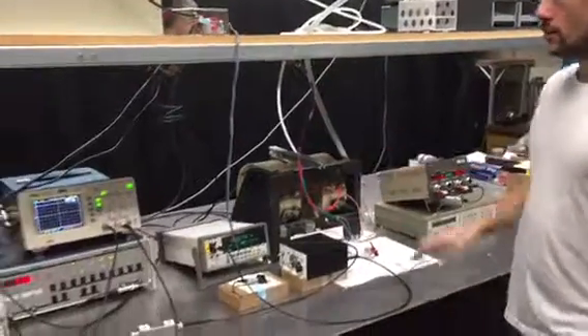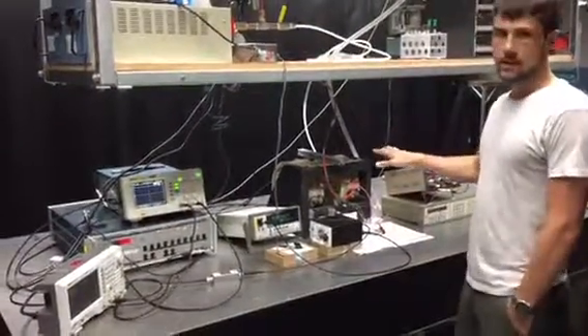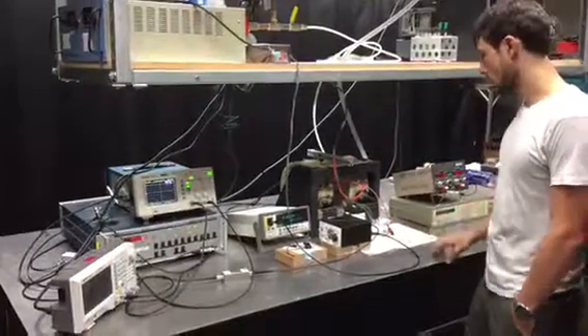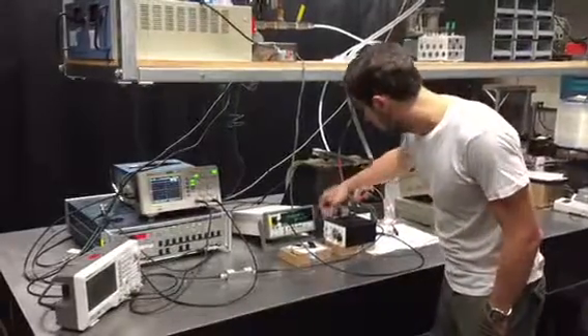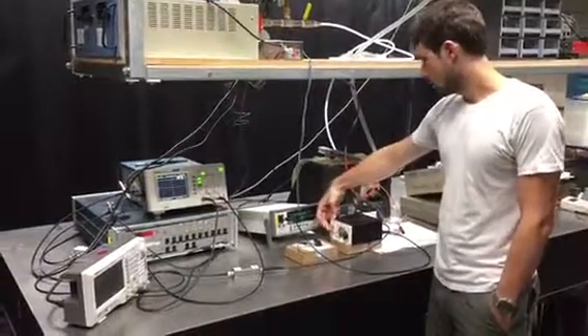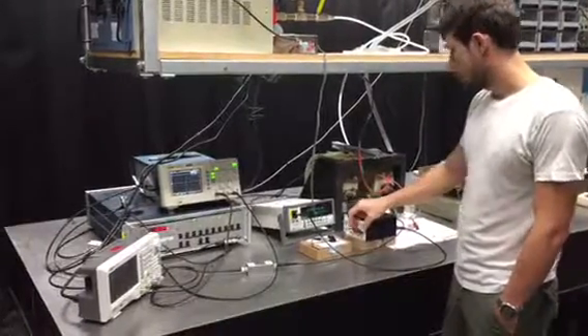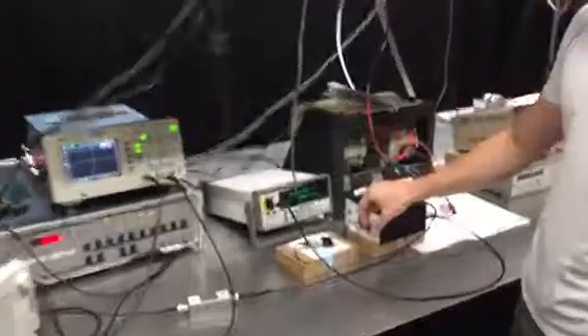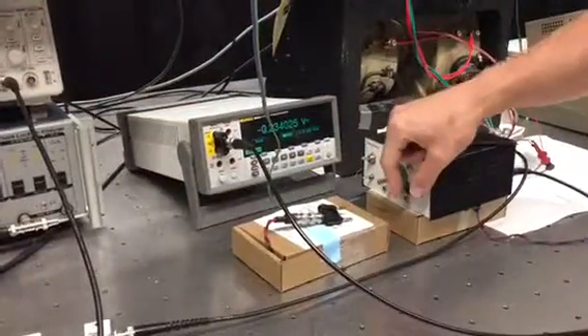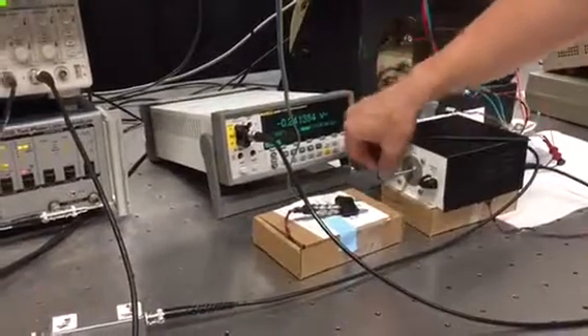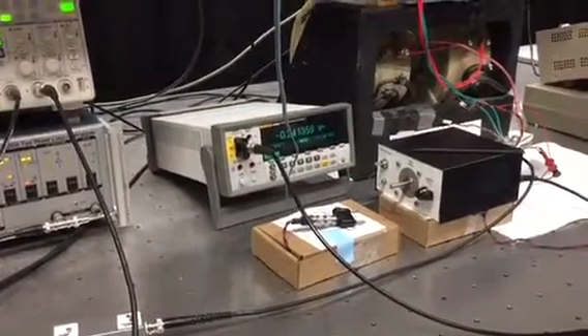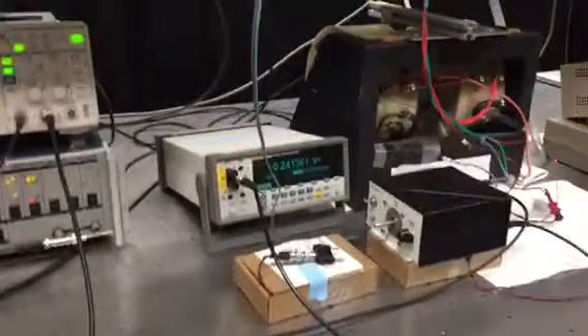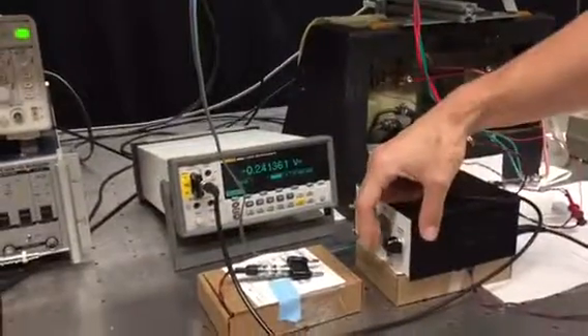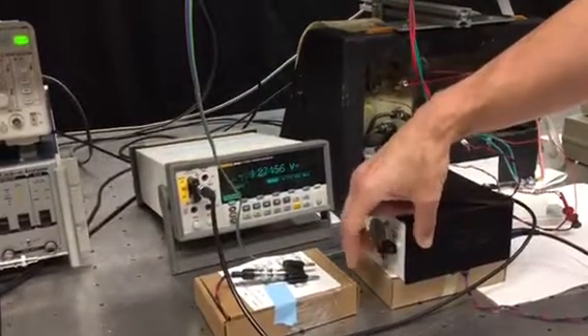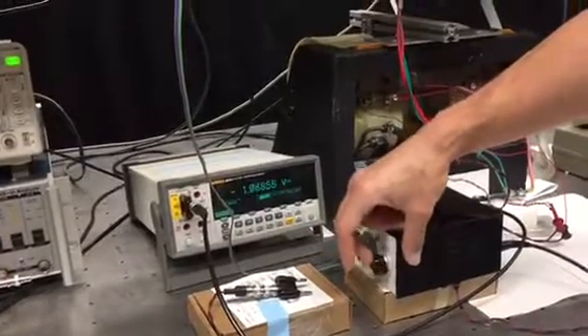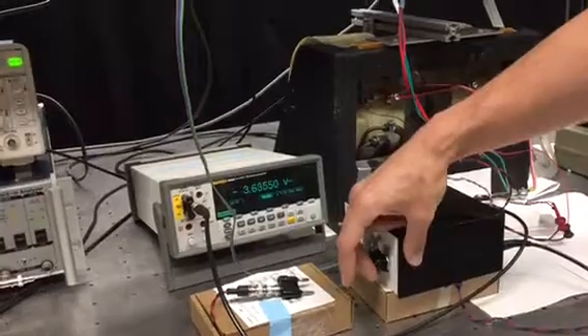So before we tune the probe and tune with the RF section, we're going to just set the magnetic field approximately and let that warm up first. So the first thing to do is we turn the magnetic field enable on. And then we turn the coarse adjust knob and we can dial the magnetic field back and forth. So once that works, we can turn the remote enable on, and now we can start cranking the field up. We know the field we want is going to come out to about 3.5 volts on here. One, two, three, and change.